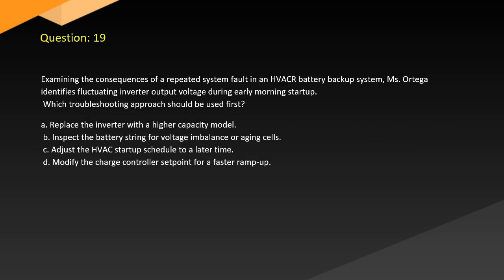Question 19. Examining the consequences of a repeated system fault in an HVACR battery backup system, Ortega identifies fluctuating inverter output voltage during early morning startup. Which troubleshooting approach should be used first? A. Replace the inverter with a higher capacity model. B. Inspect the battery string for voltage imbalance or aging cells. C. Adjust the HVAC startup schedule to a later time. D. Modify the charge controller set point for a faster ramp up.